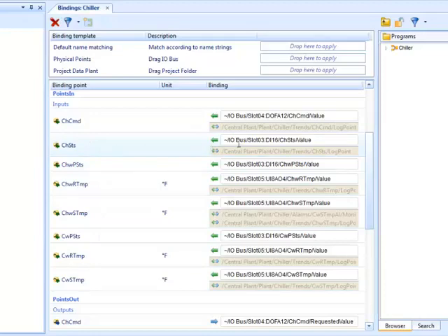Here's chiller status coming in from the I/O bus, chilled water pump status coming in from the I/O bus, chilled water return temperature coming in from the I/O bus, and so forth and so on. Here's your chiller command feedback value. It's coming from an output module, but it is the value property. That's that feedback that we were talking about.